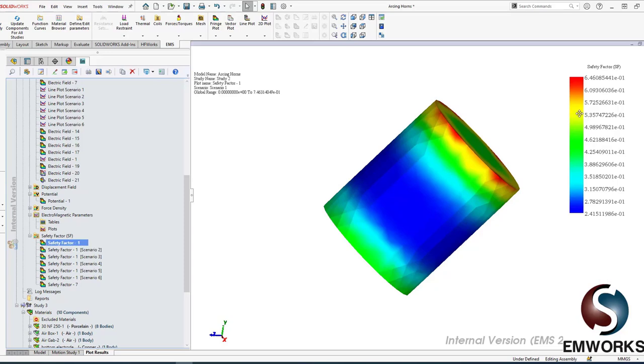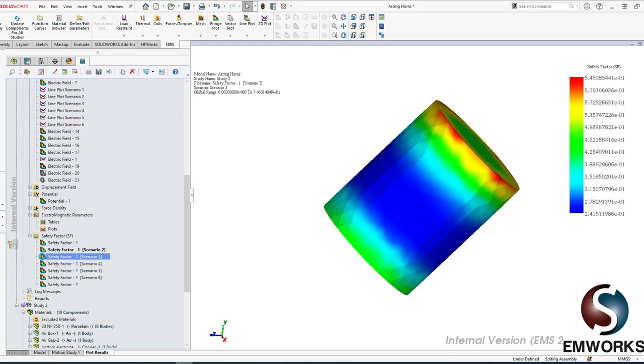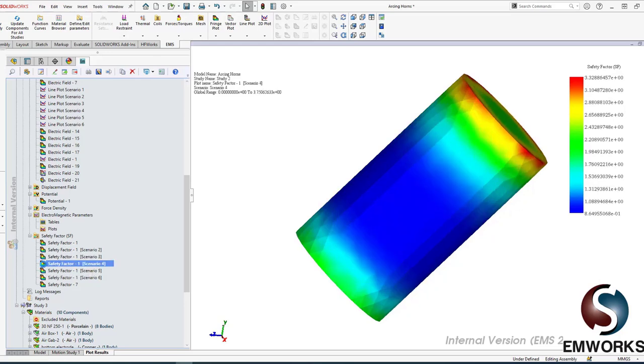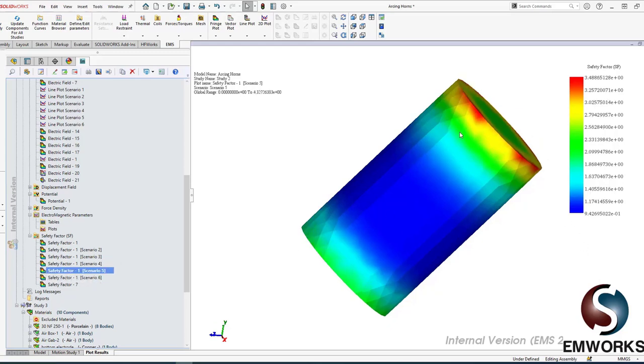So this is something we introduced in EMS; you don't find it in other software. Your safety factor in the air gap for scenario number one: you are much higher than one, so you are safe. Scenario two, scenario three, scenario four. It's the same information we presented with electric field, but now it's a more convenient way to look at it by looking at a safety factor. And ironically, safety factor in the air gap when there is a fault condition, you want it to be larger than one.